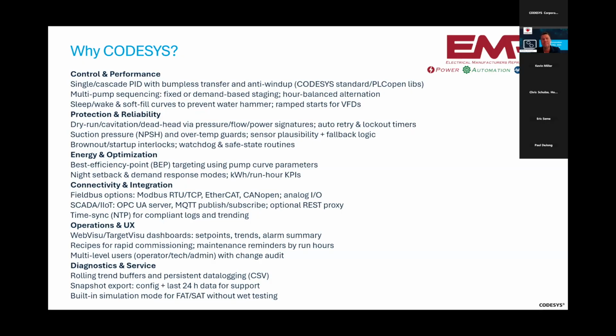Yeah, I was going to say I think the biggest benefits of CODESYS coupled with the hardware is that we don't have to be worried about communication protocols. Everything's embedded, it's integrated, it's our go-to for any solution. No, it's a good point because other hardware vendors are going to have to add a communication card. They might have to add an Ethernet card or a Modbus TCP card, or they might not be able to do MQTT directly out of the product or OPC UA. And then OPC PubSub is our latest one that we're testing with these products, to run over low bandwidth radio solutions.